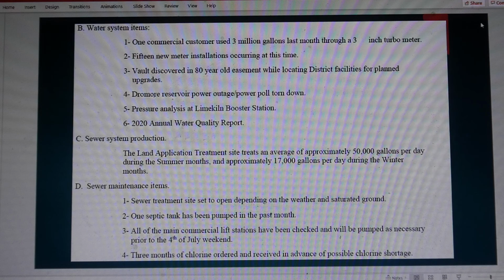It was because the power was out, the controls remembered, oh, I'm supposed to be pumping now. And it just kept pumping, so it was overflowing the reservoir. Because it was cooler weather, and it's a small reservoir, 11,000 gallons, we were able to turn the pumps off overnight until the next day when they got Kootenai Electric out. I turned it on by hand before they did to make sure we stayed in water there. And they made the repairs there.